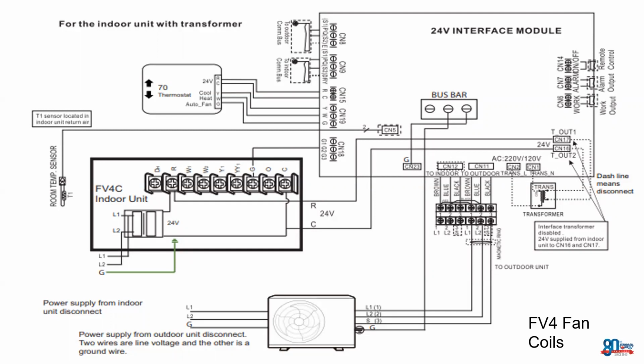What we need to wire up to is terminal G1 from the 24-volt interface on CN18 and wire it directly to G on the FV4C AHU or indoor unit. Okay, now what you'll see on here is when you have an active call for fan, this signal is going to be sent from the third-party thermostat into the interface, which then sends that signal on G1 to the G terminal at the FV4 printed circuit board, which essentially tells the fan to come on.